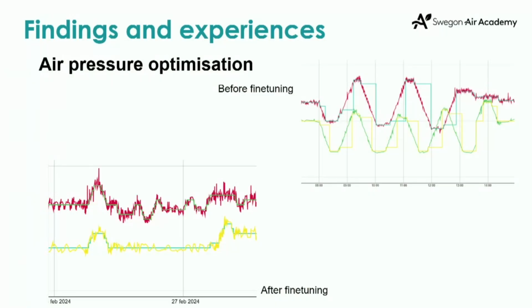Sure, that's after the system has been running for a while. If we first look at the air pressure optimization function we discussed earlier in connection to energy savings, this is a standard feature in this particular DCV system. But to get this to work as intended in this building throughout the whole system, could you tell us a bit about that, Robin?